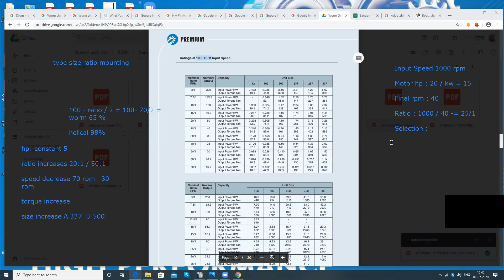Here the motor HP is 20, which in kilowatt is equal to 15. Then the next thing is the selection. You will select based on final RPM or the ratio. Here you can see 25 is to 1, 40 RPM, kilowatt capacity 3.1. Did you check the application? Not yet. So what is the application? Because the safety factor will come into the picture as we discussed. The application is given as a drum mix plant of road construction.